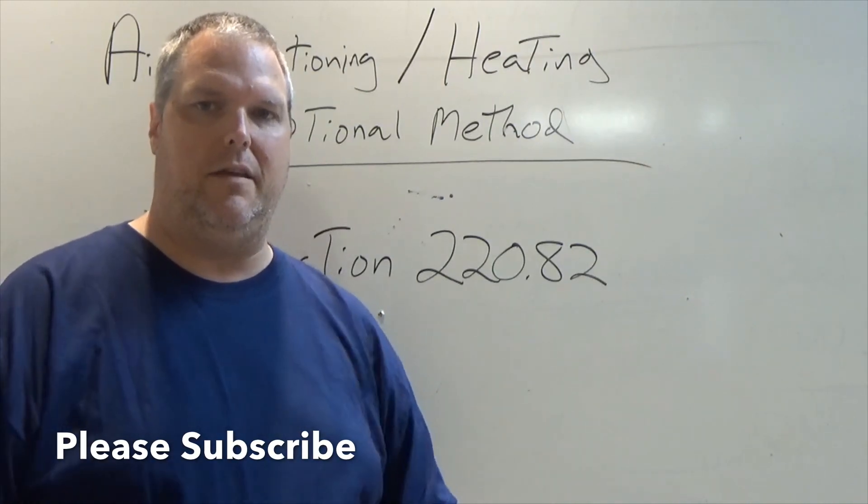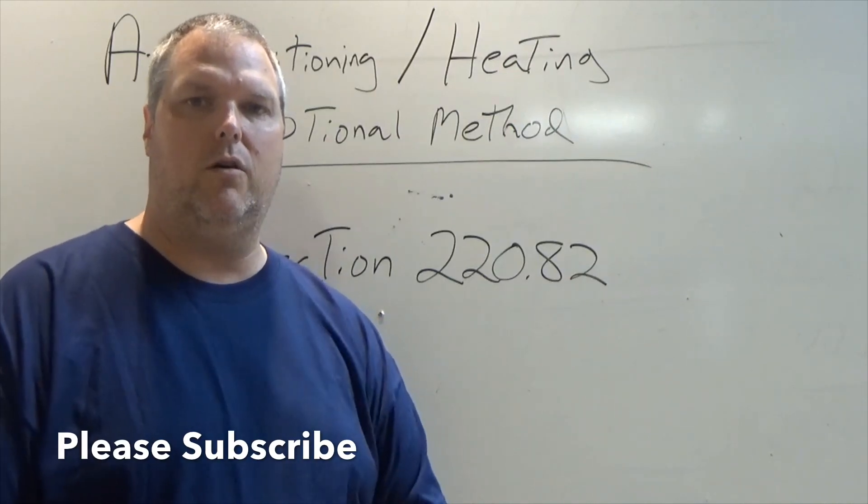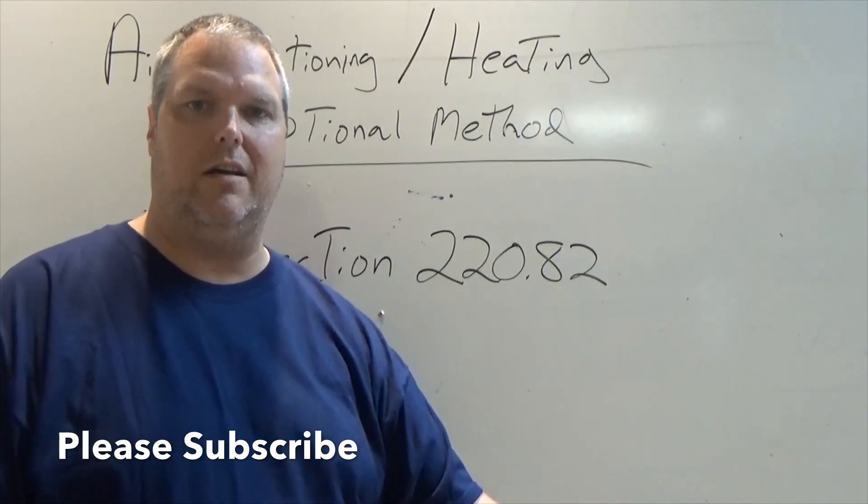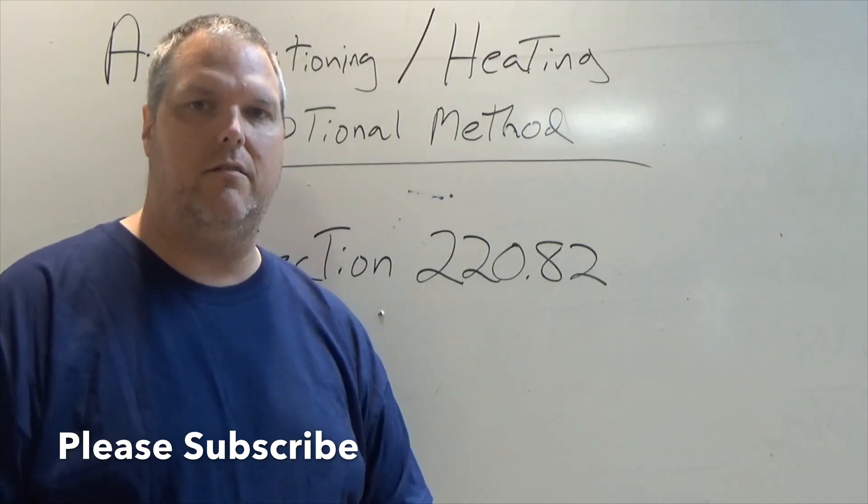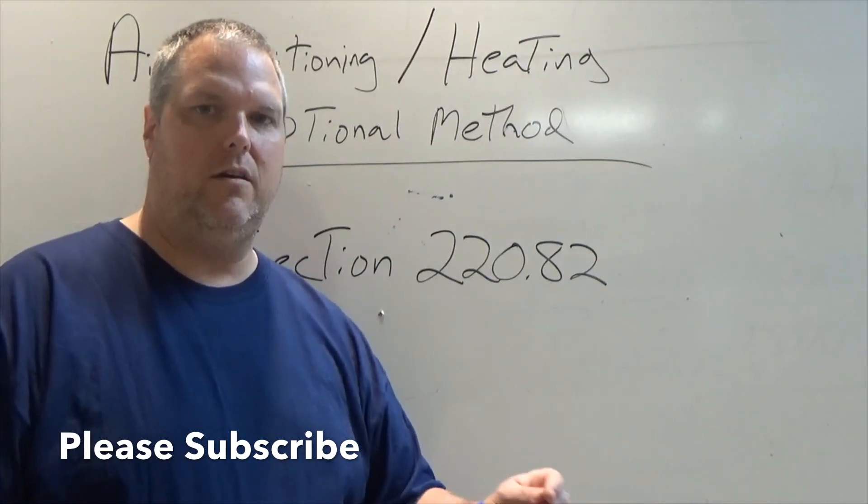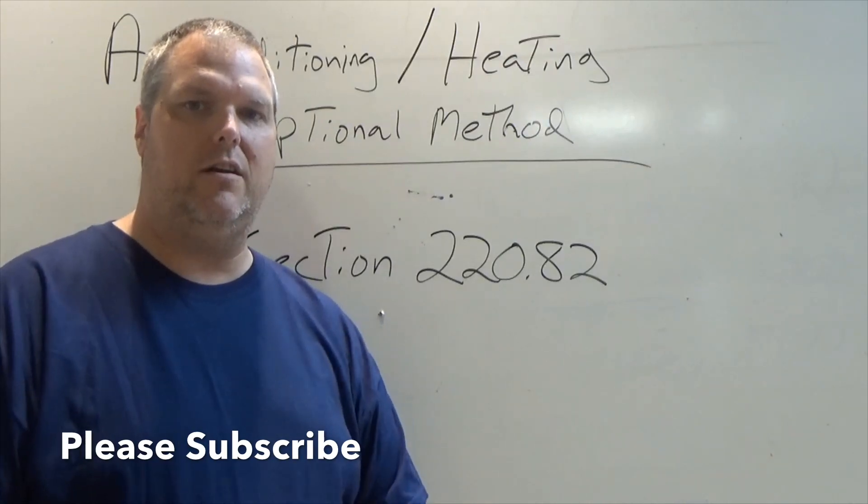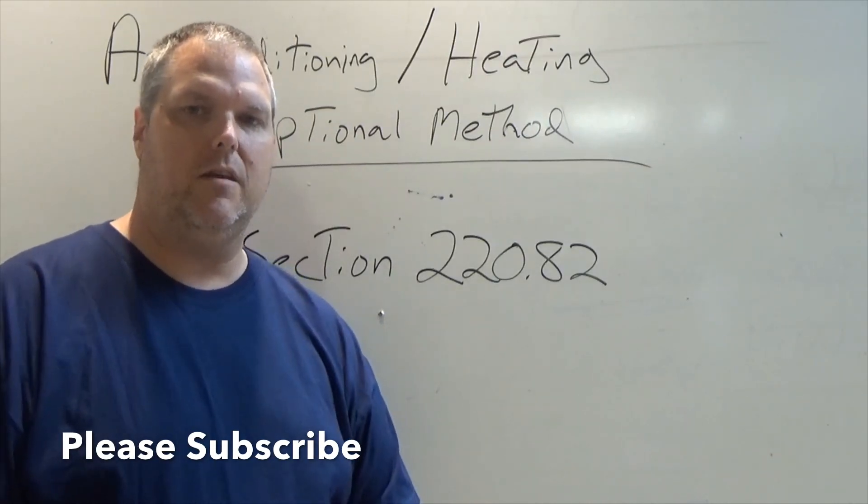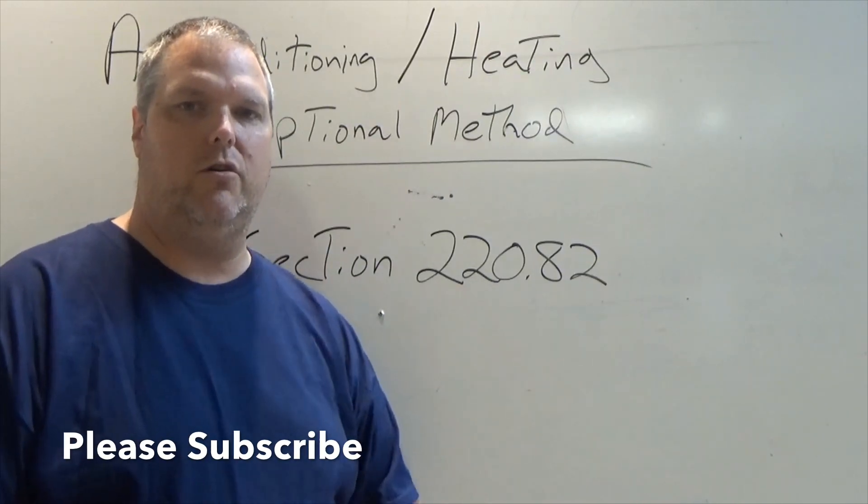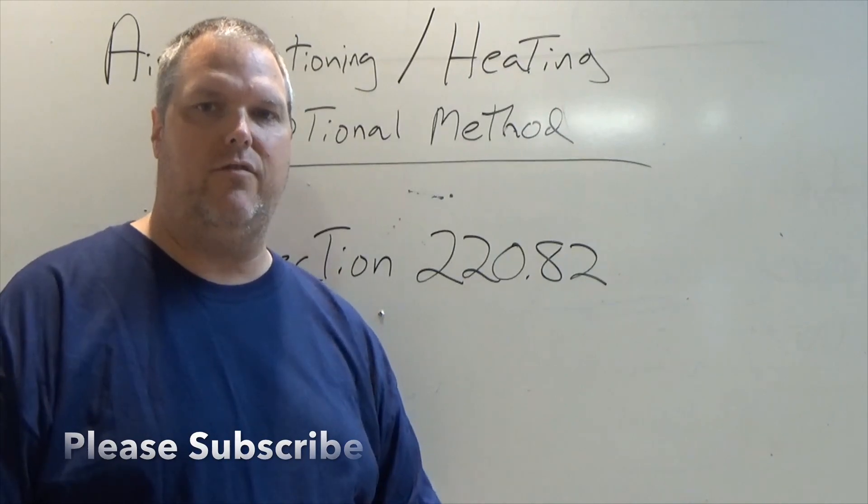What we're going to do today is discuss the different parts. Air conditioning is going to be the same. You're going to take your compressor motor. If you have a blower or an air handler that is used with heating, you also have to calculate that just like you would in the standard method. In the optional method, you're going to take the same information and use the air conditioning at a hundred percent.